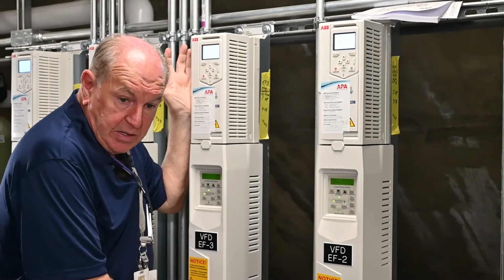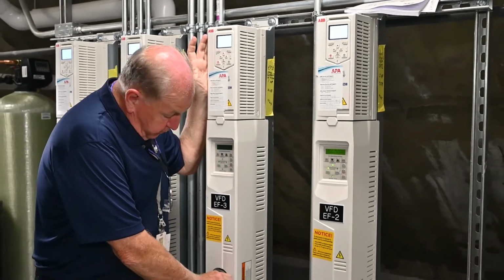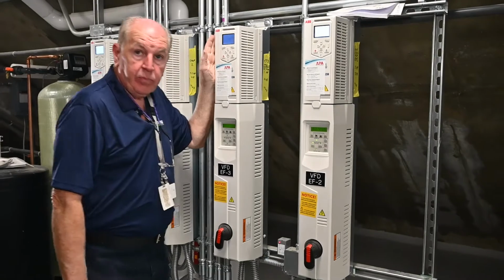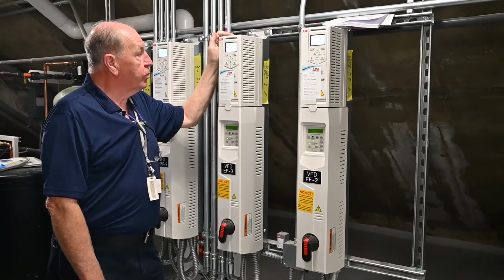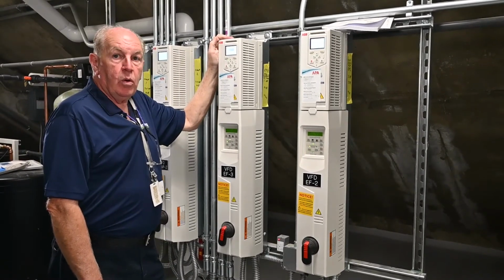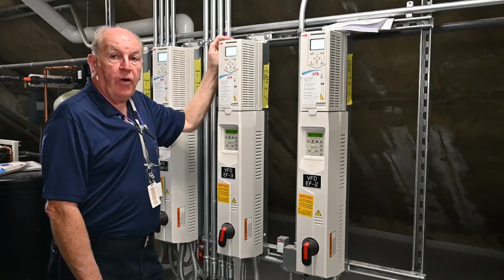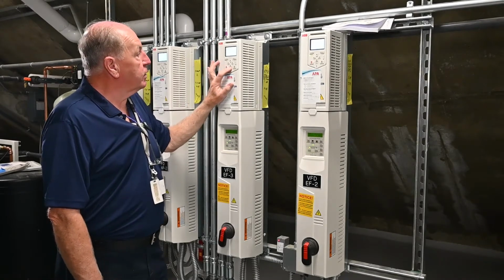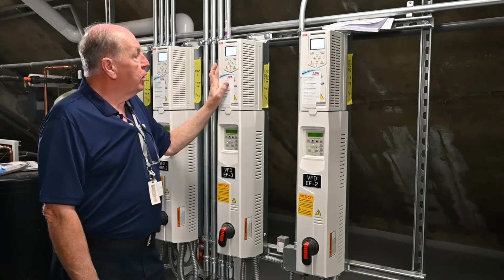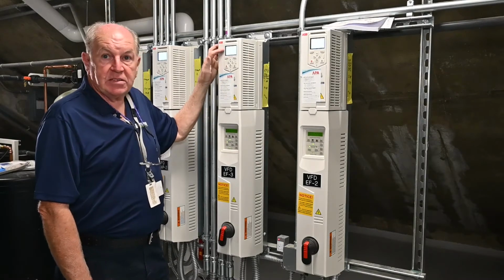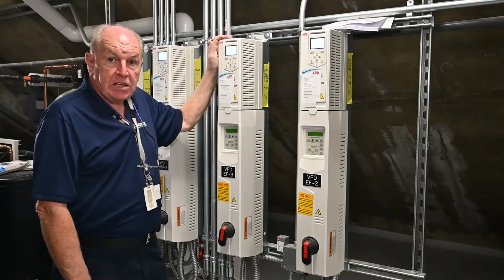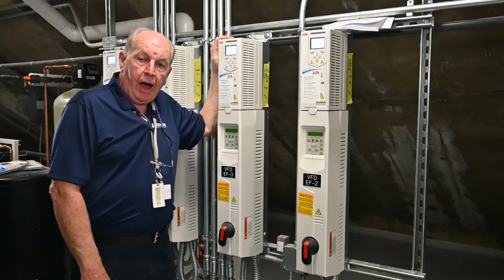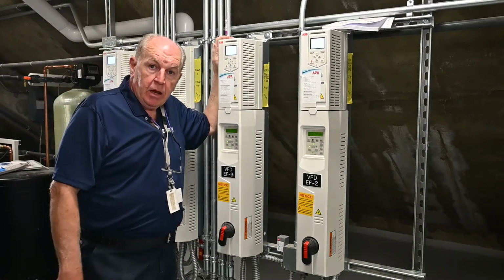And it's always easier to just recycle the power. Once the fault clears, you hit automatic. And the fan starts ramping up. This exhaust fan is on the roof. We'll go up and look at that in a minute.